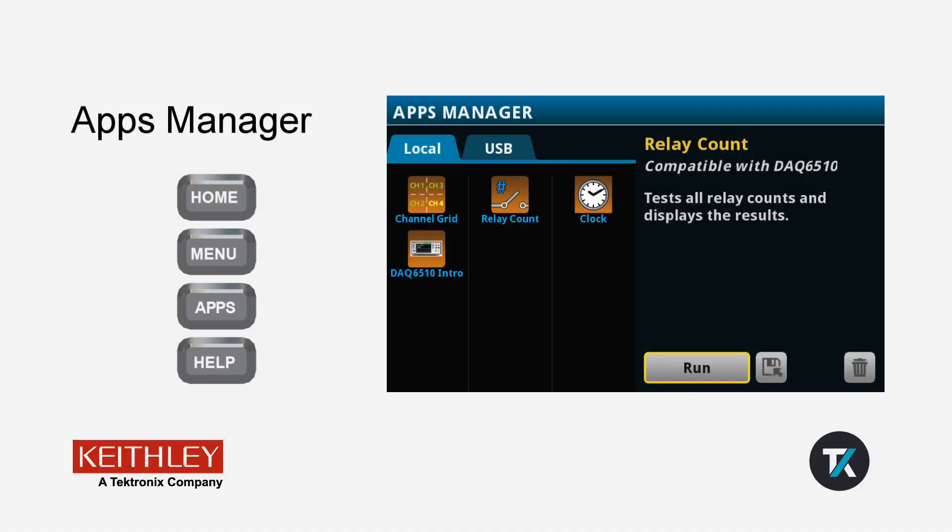The Keithley DAQ-6510 introduces a new way to interact with your instrument using applications. These apps can be downloaded from the Tek website, installed on your instrument using a USB flash drive, and accessed in the Apps Manager by pressing the Apps key on the front panel.